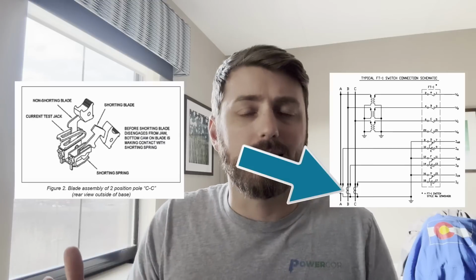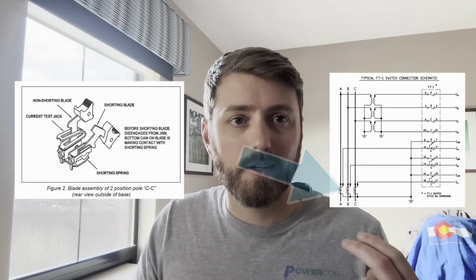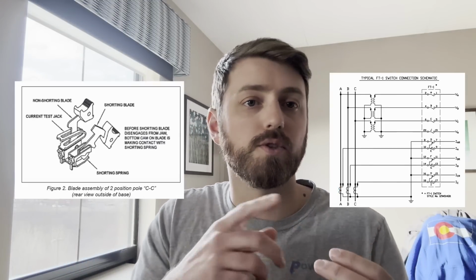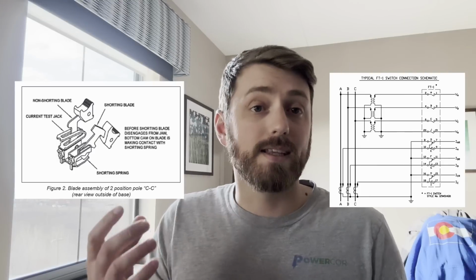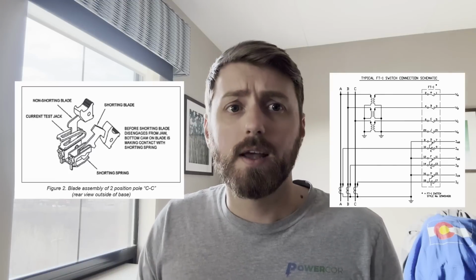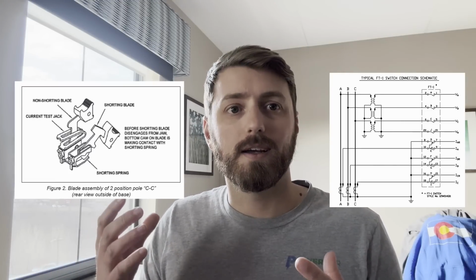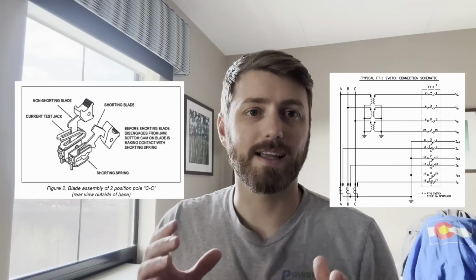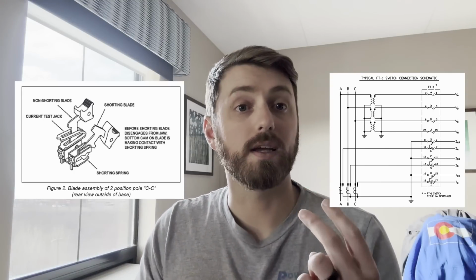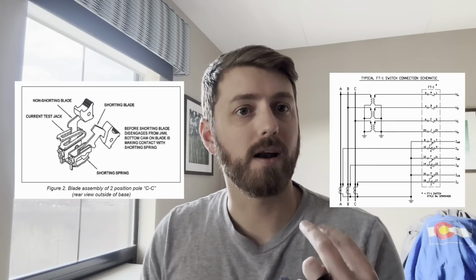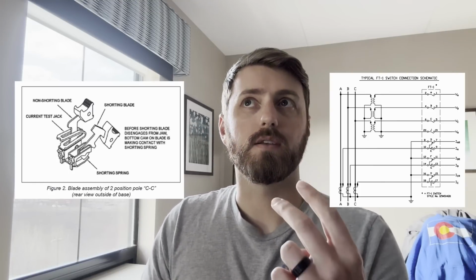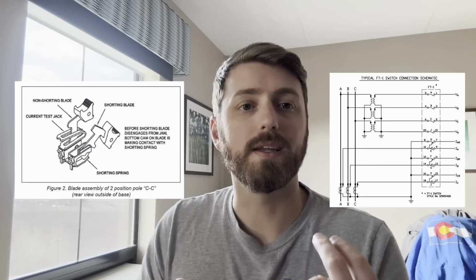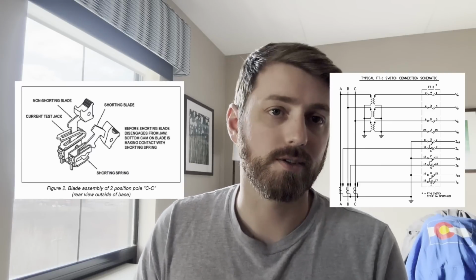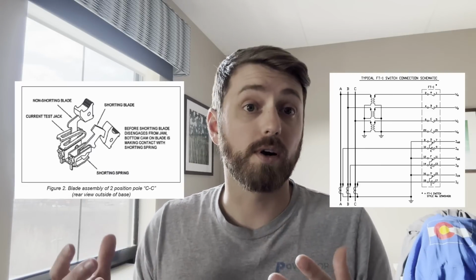Another cool feature: current sources from CTs generally need to be shorted so that you have a closed loop on the secondary. And if you're isolating a relay, well, that circuit can come open. So the FT cases had a really ingenious, very simple, very clever mechanism for shorting the CT circuit at the switch on the bottom blade side of the switch, so that no matter what order the switches were opened in, you never had an open circuit on your CT secondary. And again, that only works if the CT is wired up to the bottom, the blade side of the test switch.